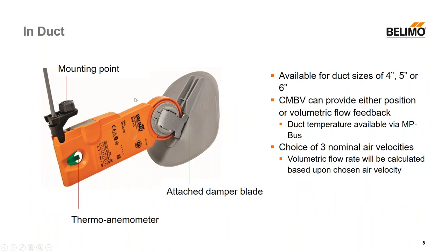We also have the in-duct actuators, which is a really nice solution. These go into your ductwork and mount with a single screw. They use a thermo-anemometer to make volumetric flow measurements and come with an attached damper blade in sizes of four, five, or six inches. The CMBV line can provide feedback in either position or volumetric flow. If you are using Belimo MP bus — a proprietary bus network from Belimo — you can also get duct temperature feedback as well, which is a nice advantage.